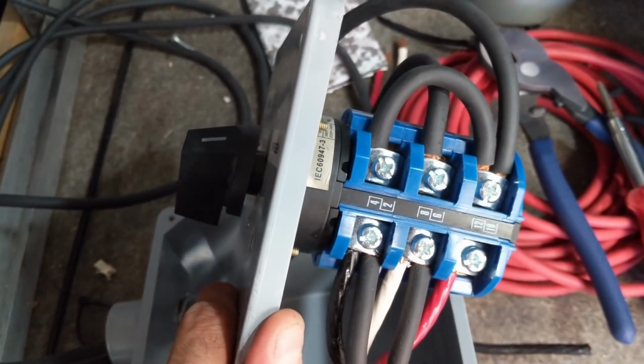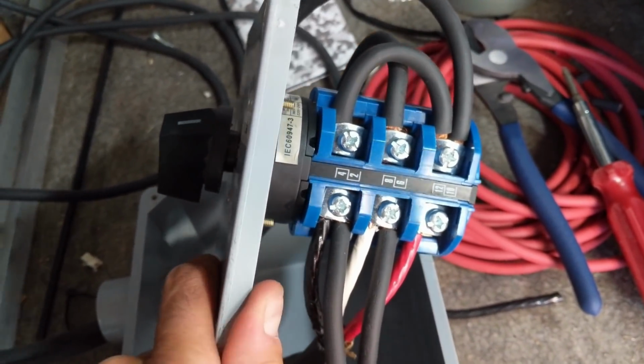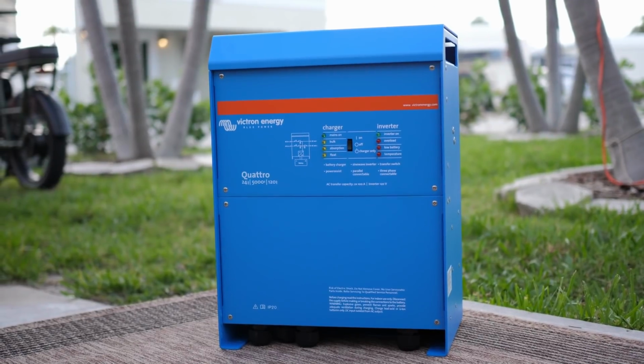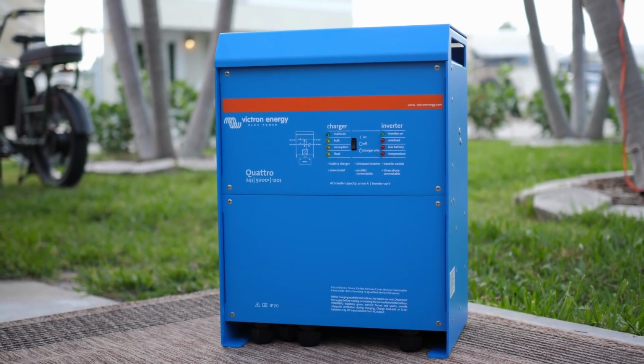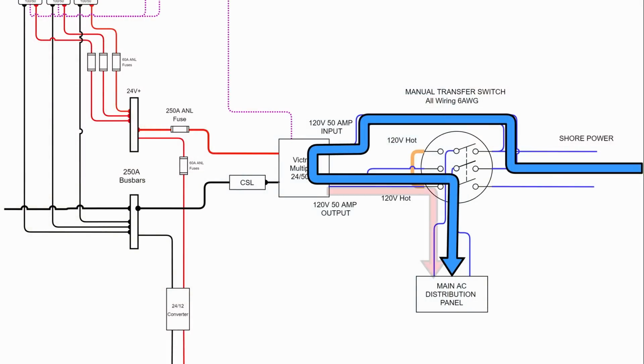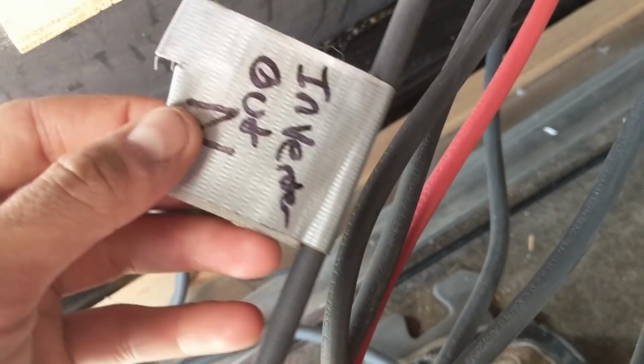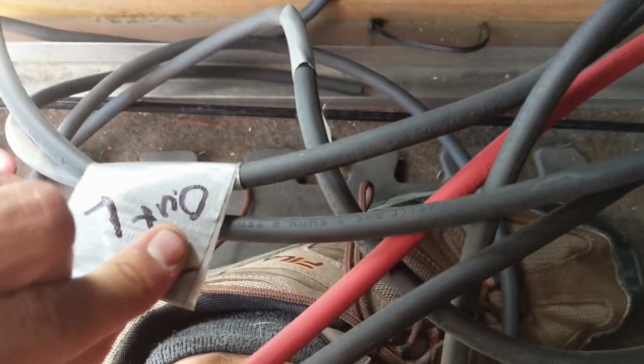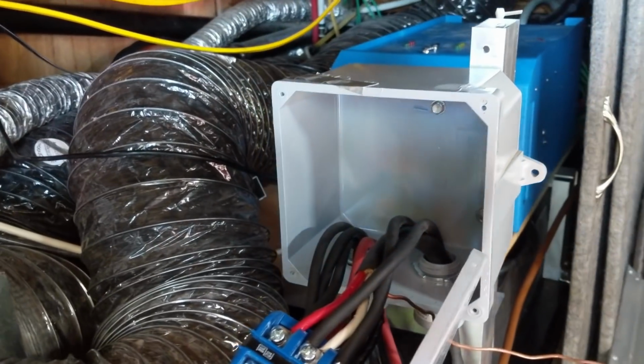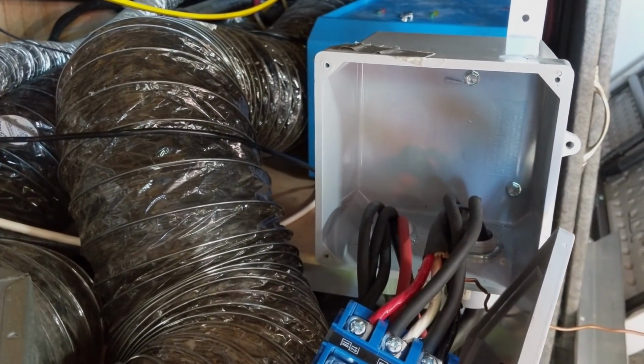With the larger inverter we'll be installing, it also has the capability to exceed 50 amps output because it's a hybrid inverter. This means it can add AC power from the solar or batteries to the shore supply, so if we exceeded the 50 amp service on a single leg, the inverter could make up the excess. Because of this, we upsized all the wiring between the inverter and distribution panel to 6-gauge wire.